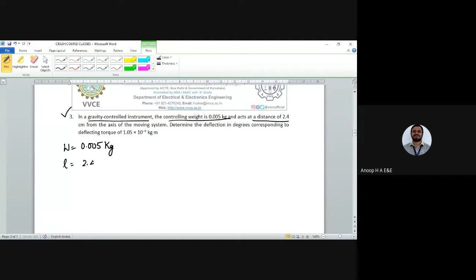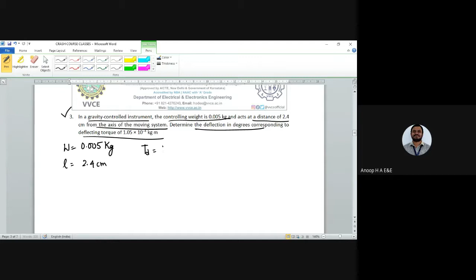You can see it is a gravity controlled instrument. Control weight is given. Control weight W, which is 0.005 kg. So it acts at a distance L, which is 2.4 centimeter from the axis of the moving system. Determine the deflection in degrees corresponding to the deflecting torque of 1.05 into 10 power minus 4 kg meter. So deflecting torque is there, which is 1.05 into 10 power minus 4 kg meter.